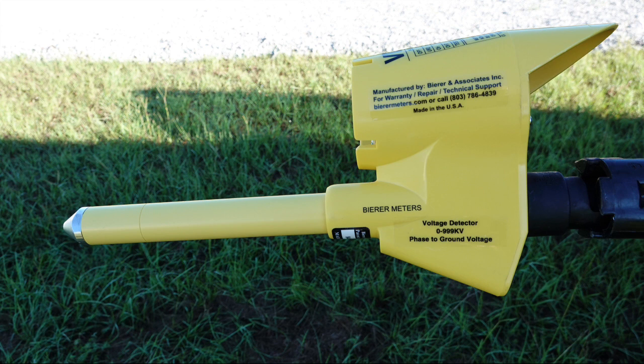But remember, the OH in OHT does not necessarily designate the voltage potential. It actually designates the height above Earth. As an example, if transmission lines come into a substation and they're less than 40 feet above Earth, the VD1000 needs to be put in the OH position, and the reverse of that is true. If distribution lines are constructed as an underbuild on transmission towers and the lines are higher than 40 feet above Earth, the meter needs to be put in the OHT switch position. This has concluded our underground and overhead demonstrations for our VD1000.